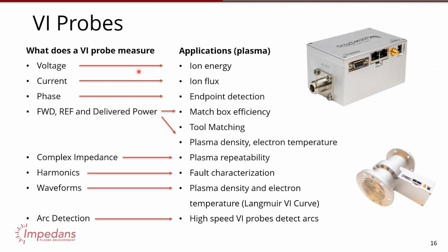So in order to enable all this, you have to calibrate this probe. I've mentioned earlier the importance of these things to measure power and measure impedance. Obviously, you have to calibrate this sensor so that it can measure those things, otherwise it's just measuring electric and magnetic fields in some way. I'm going to give you a very high-level overview of how you calibrate a VI probe—I'm leaving out a lot of details.